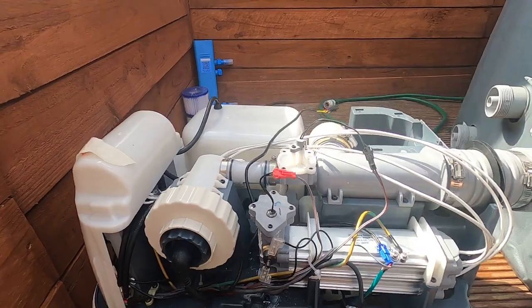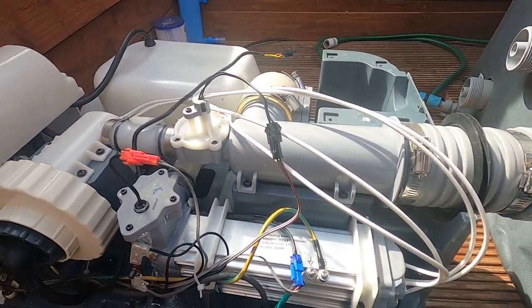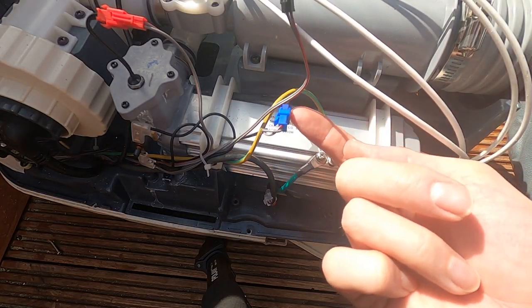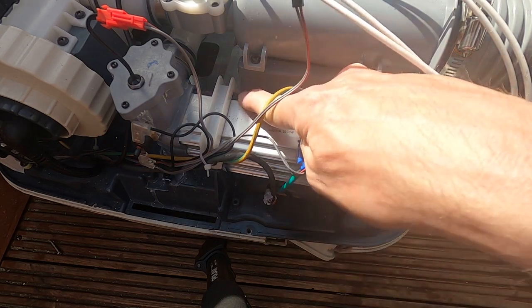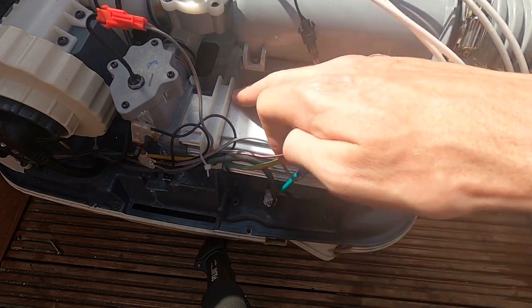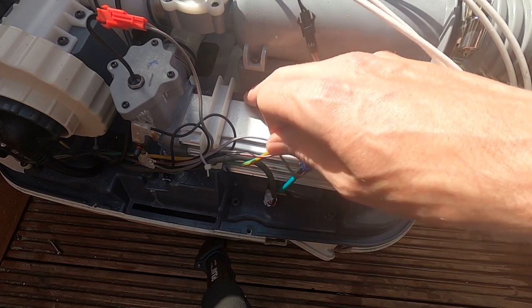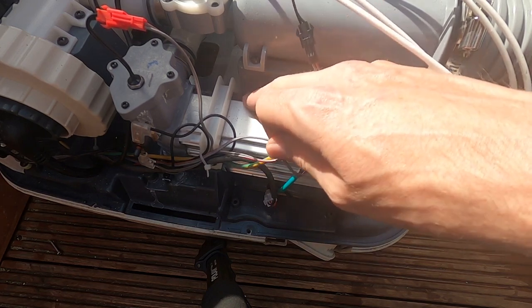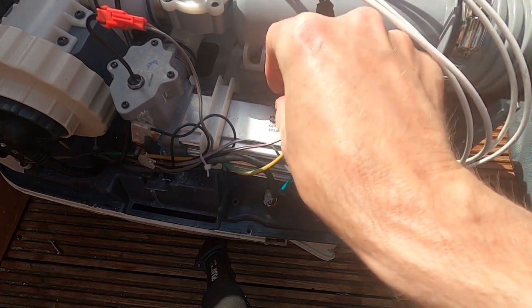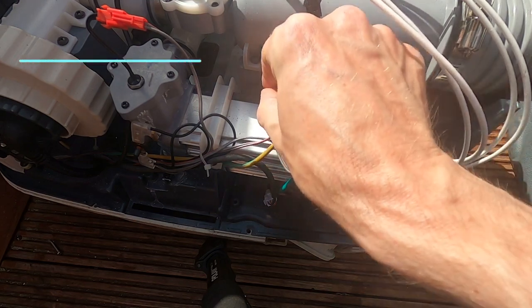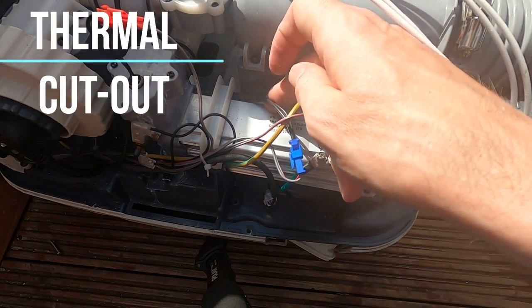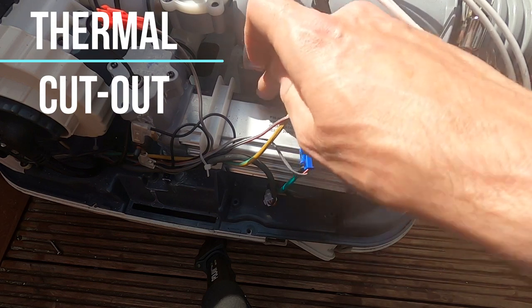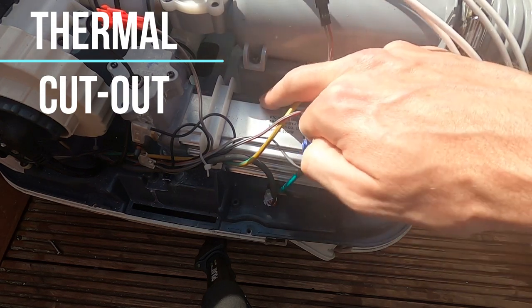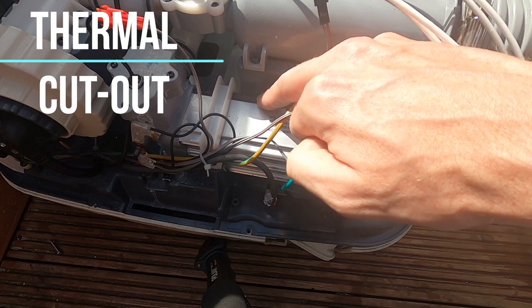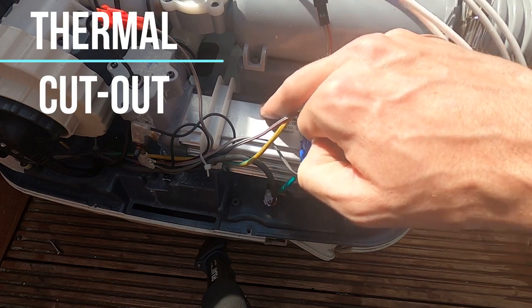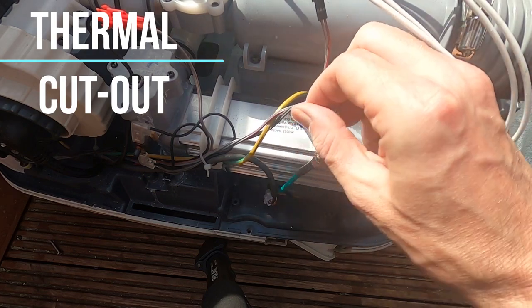Now there are a couple of other sensors that I want to draw your attention to. One is on this blue connector here, and you can see it's a little black piece of wire that's pushed down beside the temperature sensor, beside the heater element. Now this is a cutout. If this goes over temperature, it will blow and it will cut out, and this is a safety feature. Now if you find that everything looks like it's working but your heater isn't heating up, that is one of the culprits.